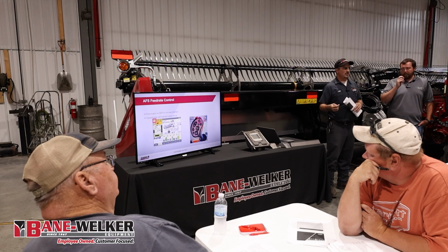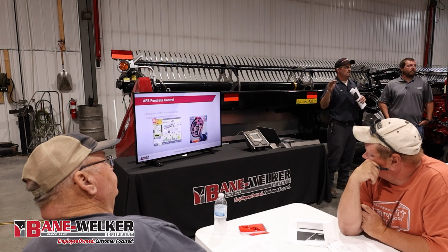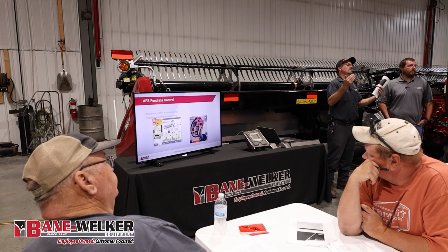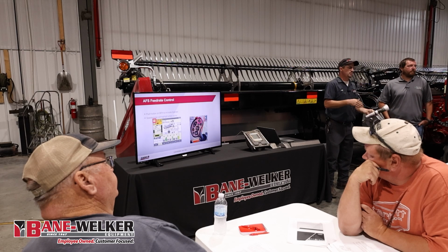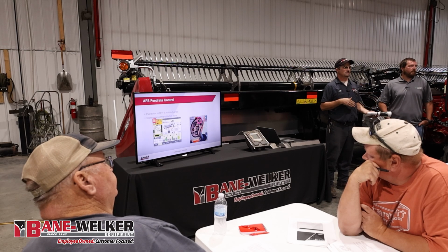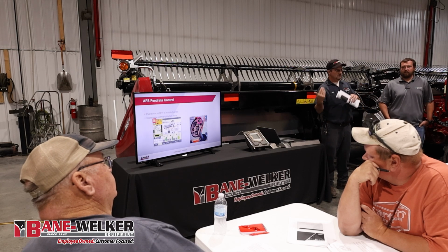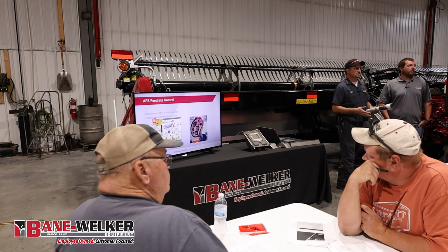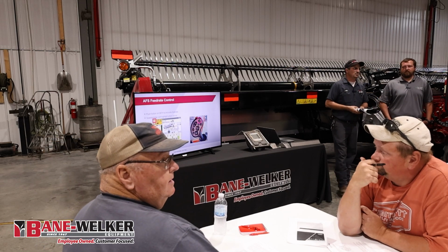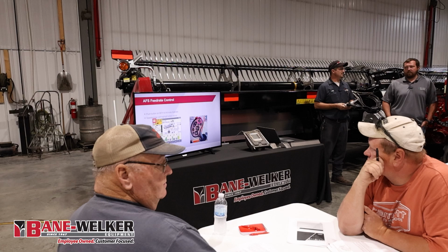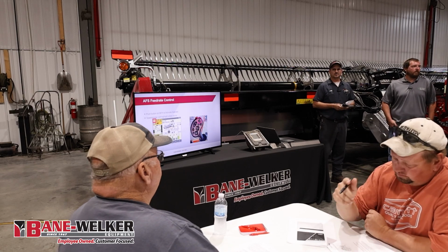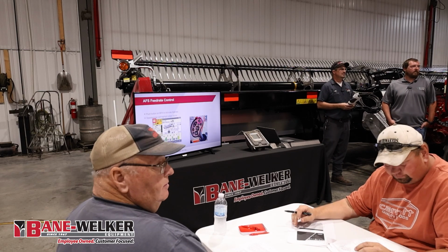I personally would recommend if you're having issues and the feed rate's not wanting to run consistent, go back and start with the 0 cal again, because we don't really know which calibration's causing issues or what's changed. Go ahead and do your 0 cal, then go back and do the other cal. So technically both calibrations together, you've got about 17 seconds of your life that it's taken to do this - and that's good for like 3 hours.